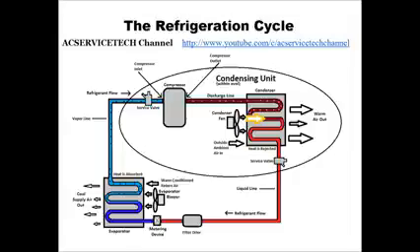Right after the saturated state, it turns into a complete liquid, until it comes out right next to the service valve. The temperature decreases as it's rejecting heat. The temperature decrease in liquid form is called the subcooling.